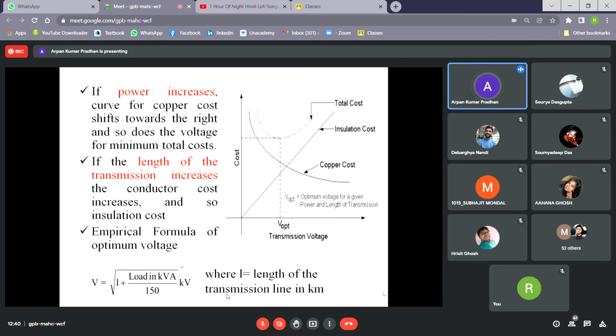If you draw the variation of cost due to copper loss with transmission voltage, the copper cost decreases with transmission voltage. And if you draw the insulation cost with transmission line voltage, as the voltage increases, the cost also increases, shown by a straight line. If you combine these two, you can see that at lower voltage levels, the overall cost, due to both copper cost and insulation cost, is higher. As you increase the voltage level, the overall cost decreases and reaches a minimum value.